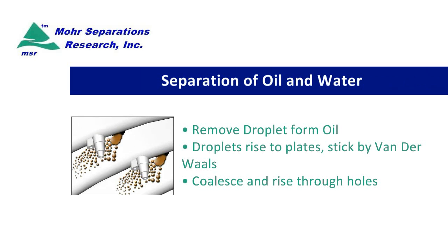Basically all oil water separators operate utilizing Stokes Law. They remove droplet form oil. The droplets rise to the plates according to Stokes Law and stick by Van der Waals forces. These are very weak molecular level forces so they don't stick very well.